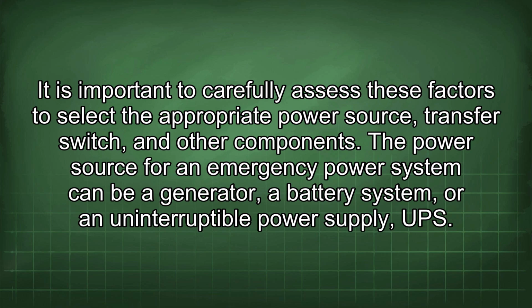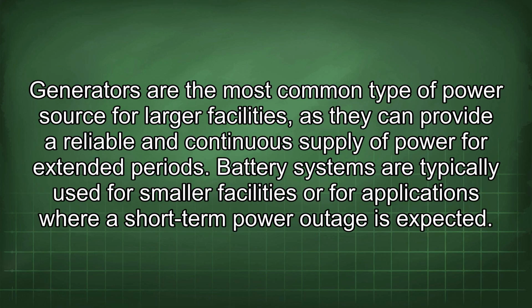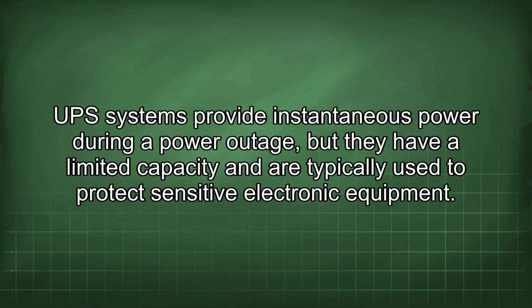The power source for an emergency power system can be a generator, a battery system, or an uninterruptible power supply, UPS. Generators are the most common type of power source for larger facilities, as they can provide a reliable and continuous supply of power for extended periods. Battery systems are typically used for smaller facilities or for applications where a short-term power outage is expected. UPS systems provide instantaneous power during a power outage, but they have a limited capacity and are typically used to protect sensitive electronic equipment.